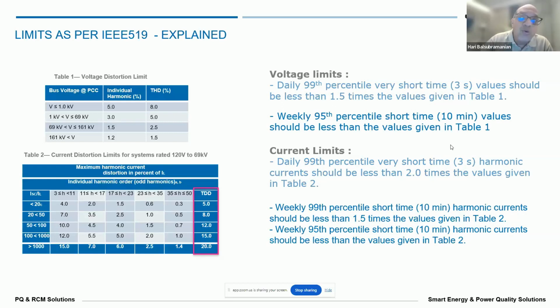Say, for example, ISC by IL: ISC is the short circuit level at the point of common coupling, and IL is the average load over the 12 months period, what we have consumed, which I talked about when we were discussing TDD. So depending on the ISC by IL value, that is, the strength of the grid at that point of common coupling, the TDD value varies. The higher the ISC by IL value, the higher the TDD limits you can have. So there are multiple limits which need to be followed for IEEE 519.